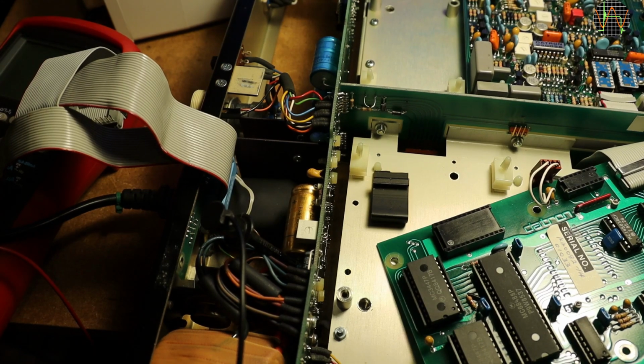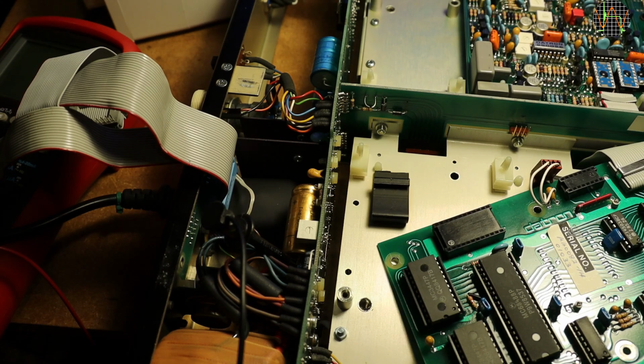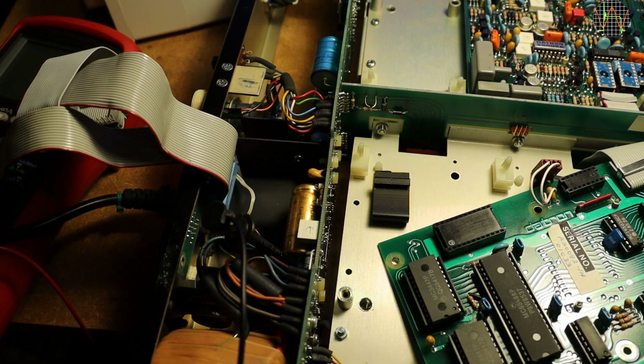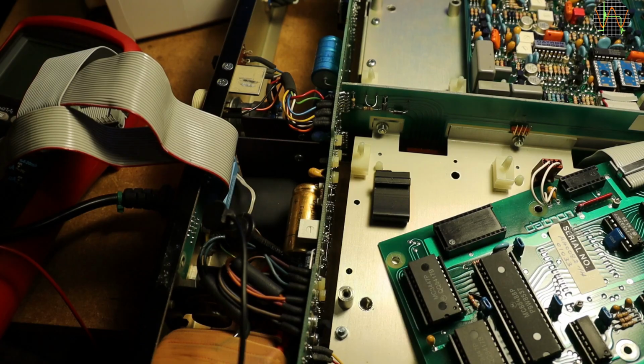I followed the usual method by disconnecting PCBs and seeing if the fault disappears. That would indicate the short is on the removed board. Well, it's not the GPIB bus interface because the fault is still there. This was just the beginning of an exhausting search that I just want to summarize here.